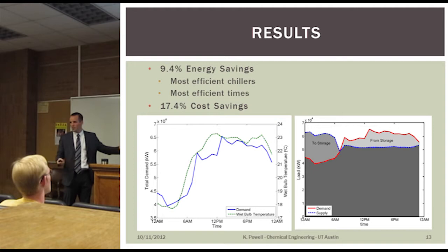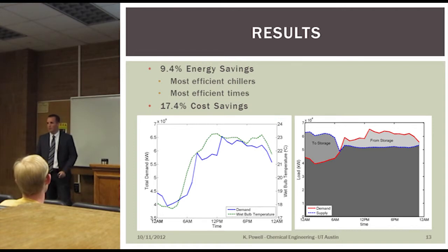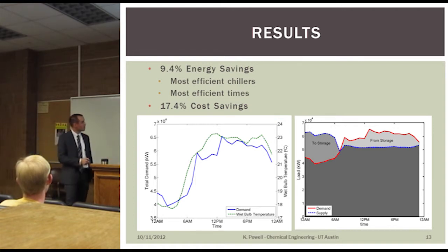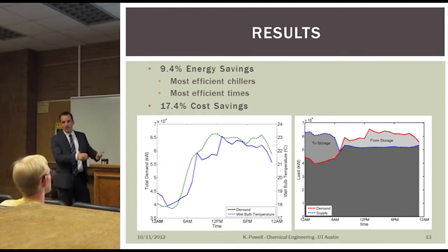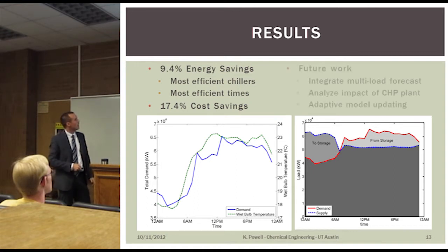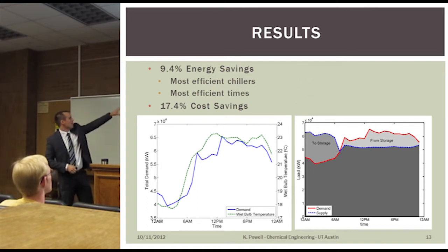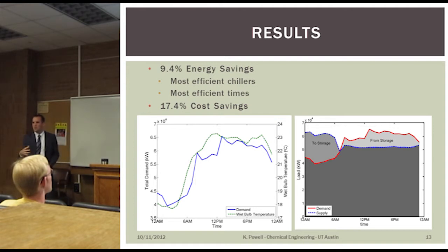Those chillers operate a lot more efficiently at lower wet bulb temperatures—think of Carnot efficiency. Your thermal cycle is better if you're rejecting heat at a lower temperature. So our chillers operate more efficiently here, meaning we can shift a lot of our load to those early hours, store that energy, and then later in the day when we have peak cooling, we can harness all that extra energy.